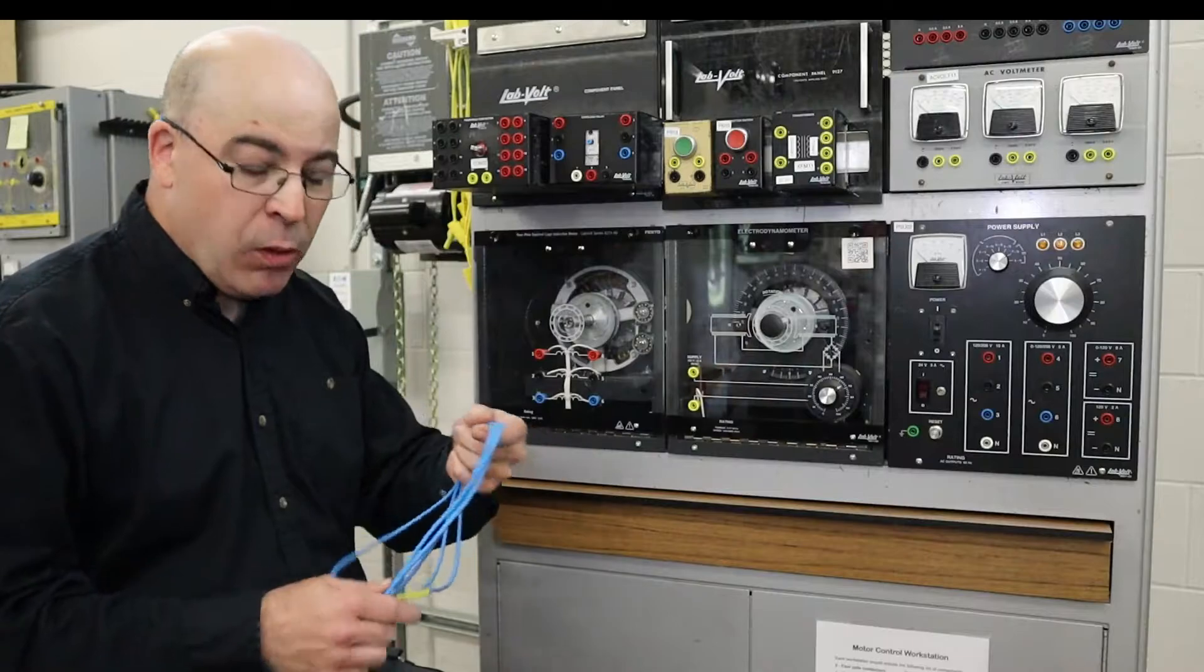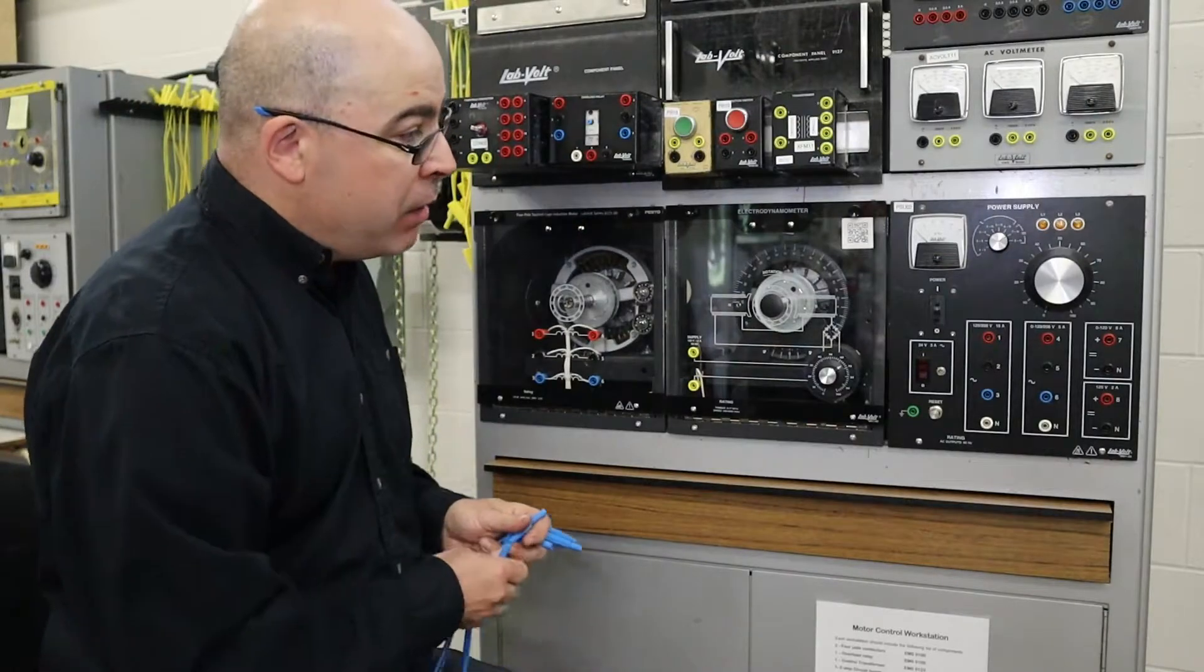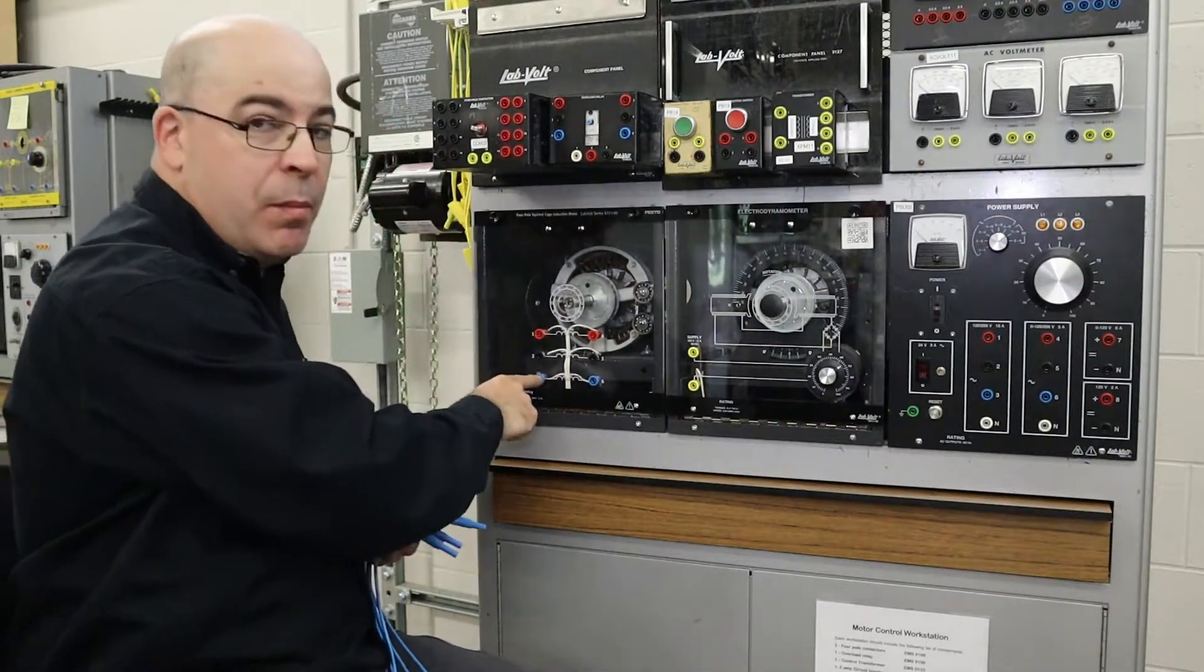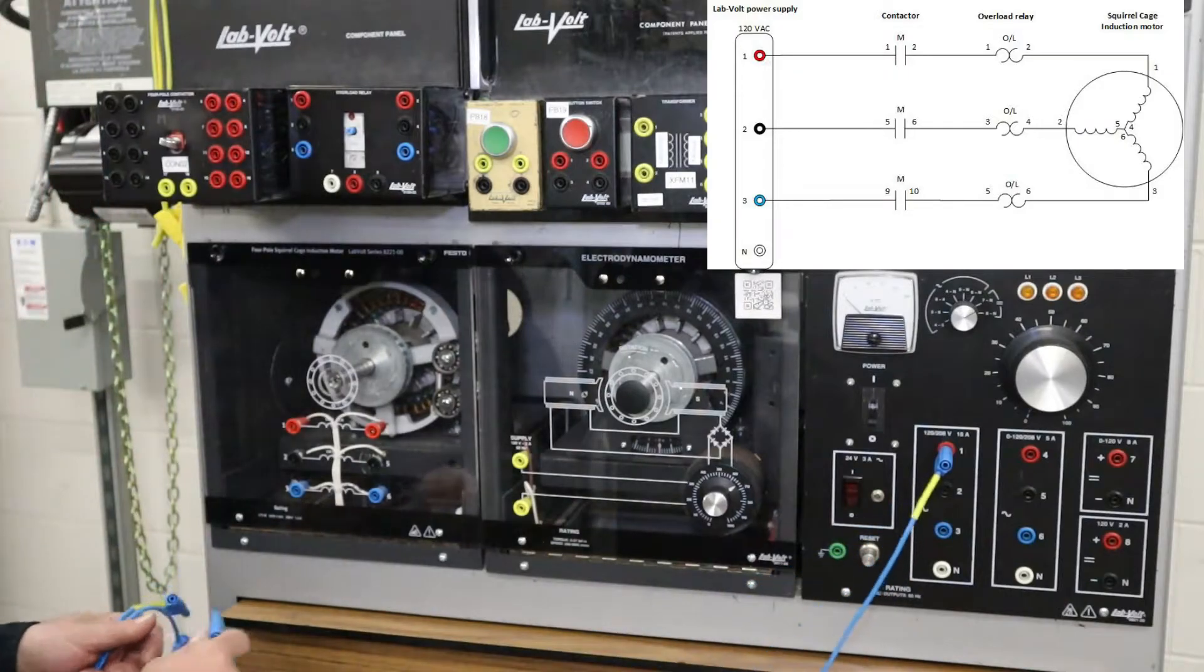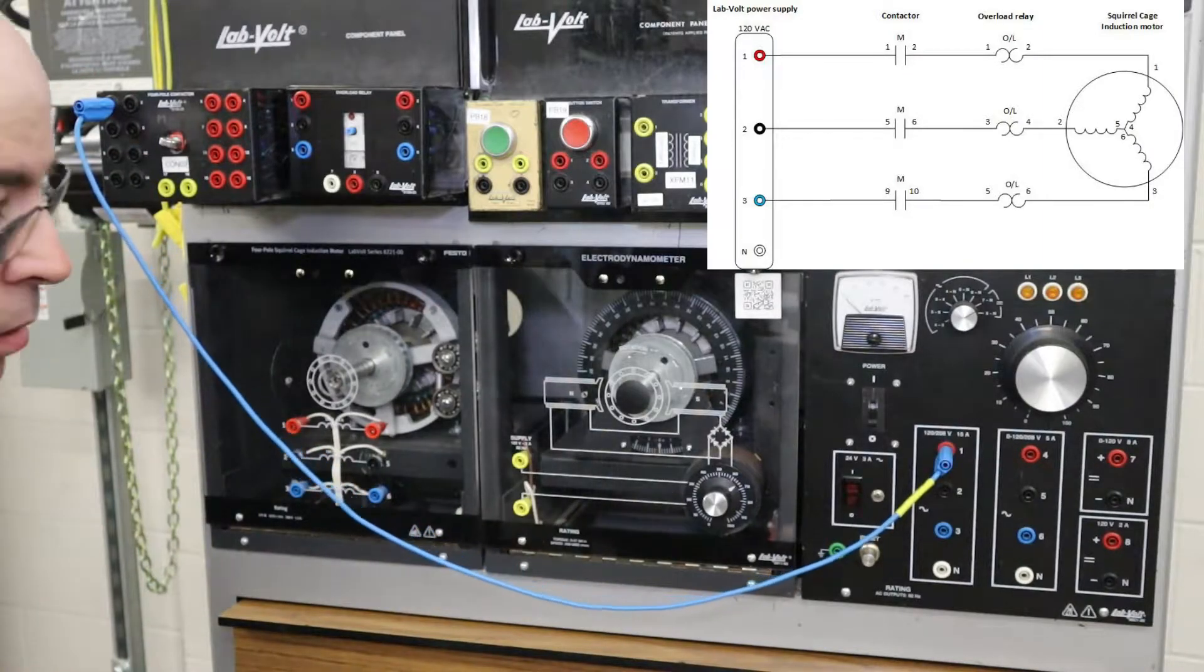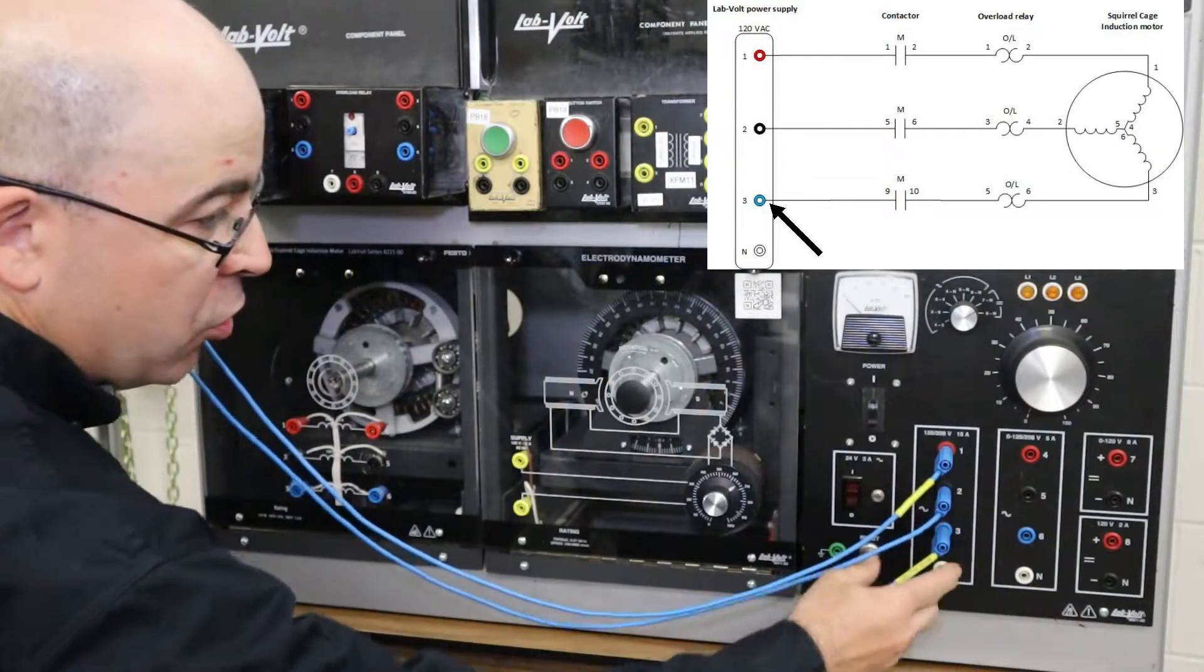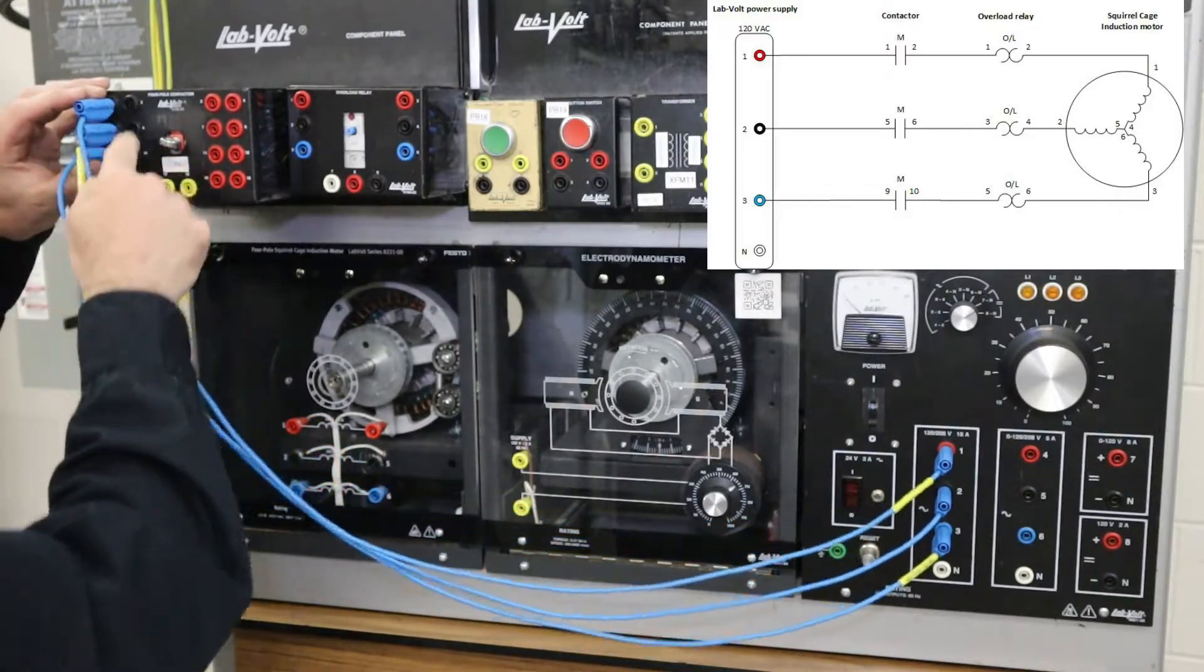First, we're going to get started with some blue test leads. We're going to run from the power supply to the contactor, from the contactor to the overload relay, and the overload relay to the motor. We're going from terminal one to the first contact, number one, then terminal two to the second normally open contact - terminal five - and terminal three from the power supply to terminal nine, so that there are three normally open contacts.